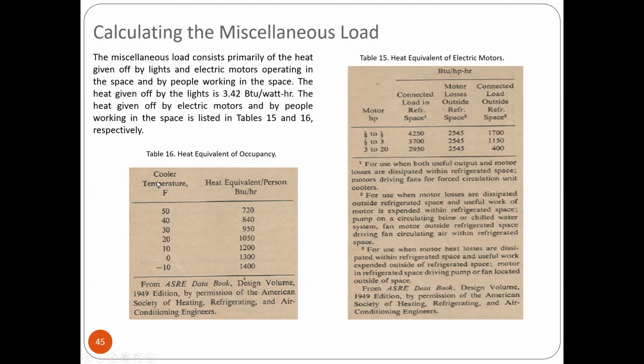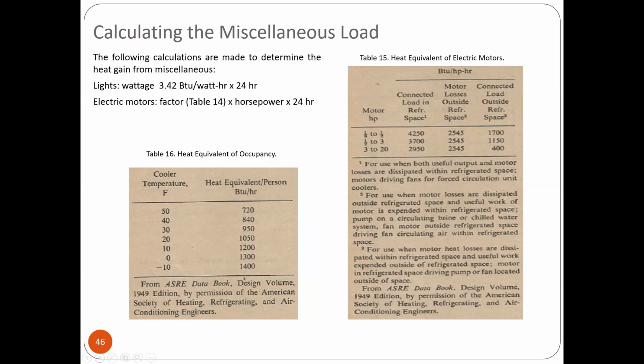Andito siya. Cooler temperature. Ayan. So, ang heat equivalent per person ito. Okay. So, motor losses. And then, may notes. Basahin na lang yan. So, the following calculation are made to determine the heat gain from miscellaneous lights. Wattage times 3.42 BTU per watt hour times 24. Electric motor is the factor, table 14. Horsepower times 24.